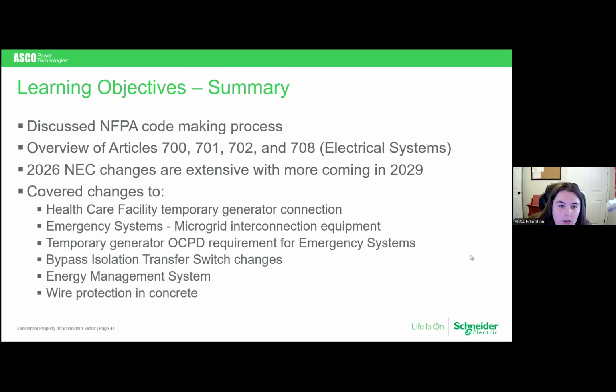Next question: 700.6(D) item 3 states that if the bypass equipment is manual or non-automatic, it shall be actively supervised while the automatic transfer equipment is disabled for servicing. Is it possible to avoid the supervision with design or installation provisions? Can the bypass be automatic?